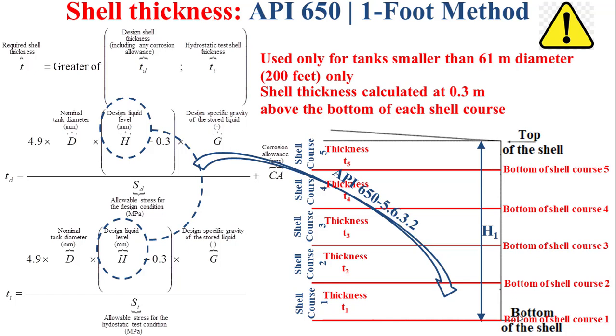The required shell thickness t1 is then the greater of td1 and tt1. Similarly, to determine t2 for shell course 2, we use h2 — the height from the bottom of shell course 2 to the top. In the same way, we determine t3 based on h3, t4 based on h4, and t5 based on h5.